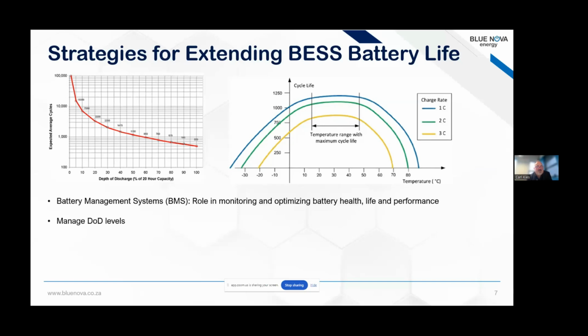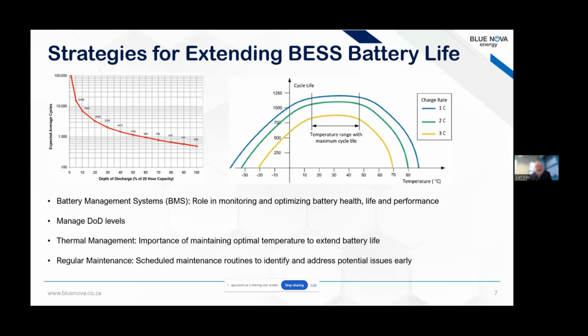You've got to manage your depth of discharge levels and thermal management. I cannot stress the importance of that - you must have a thorough thermal management system in place. And obviously regular maintenance, where you can identify and address potential issues early. This includes simple things like cleaning filters for cooling inverters. If you don't do that, you will lose cooling efficiencies.